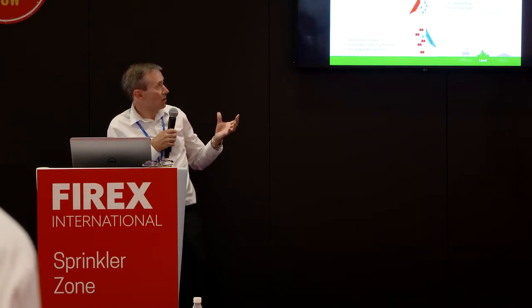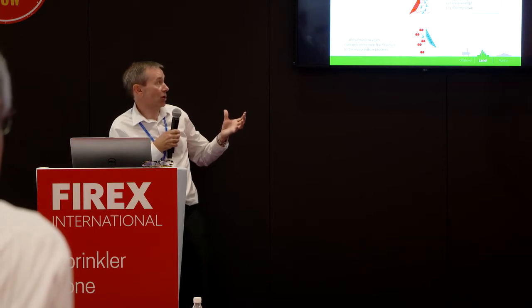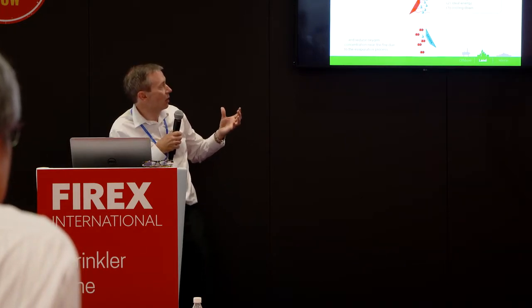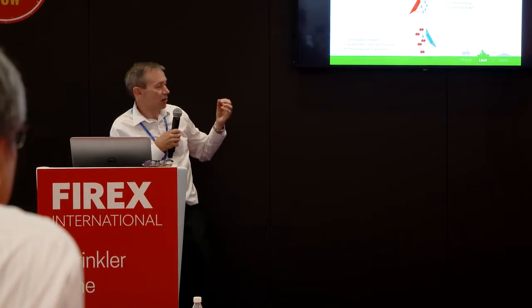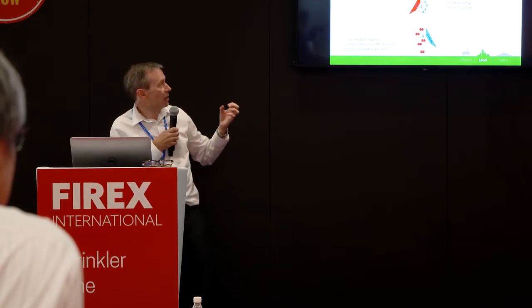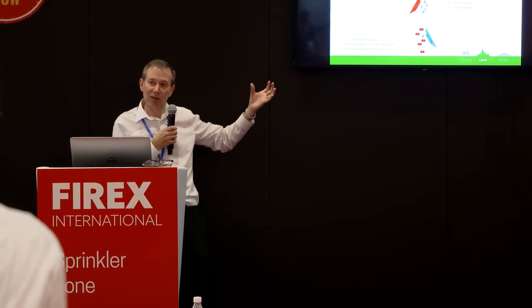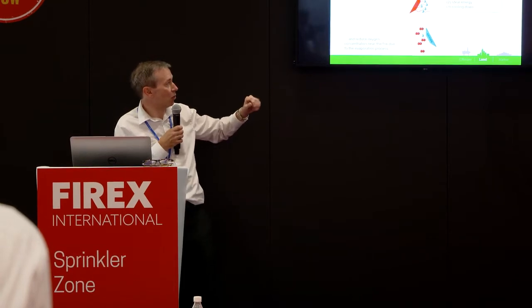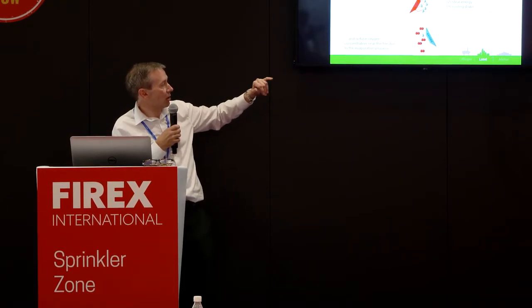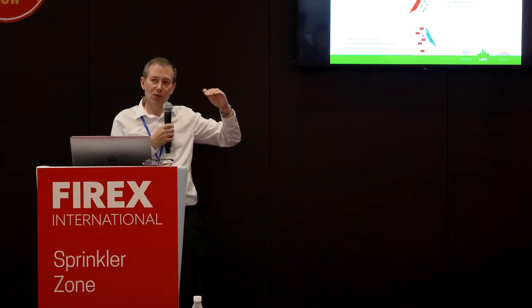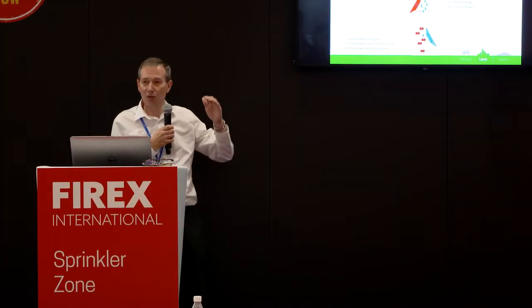The water mist itself works on the fire triangle in 2 main sides of it. Obviously, you've got the heat side of it. It takes the energy out of the heat and cools it down, that side of the triangle. But then also, as I said earlier, it reduces the oxygen levels very slightly within the room, allowing the fire to be extinguished and put out.